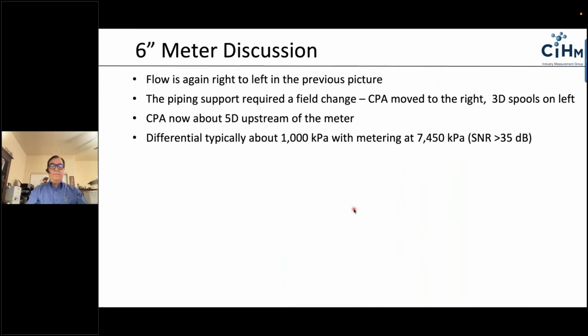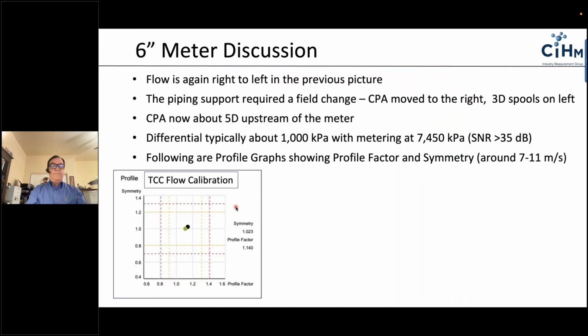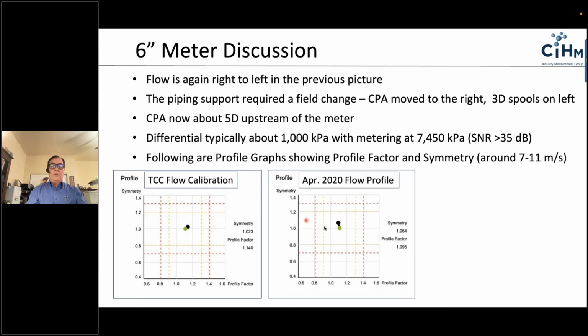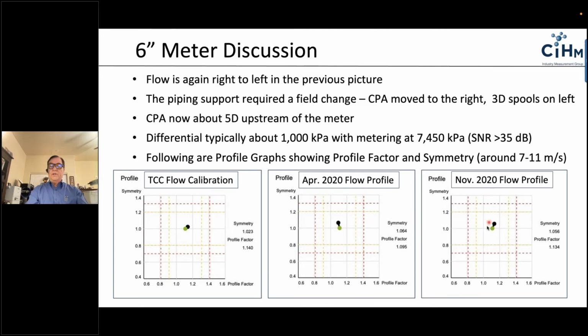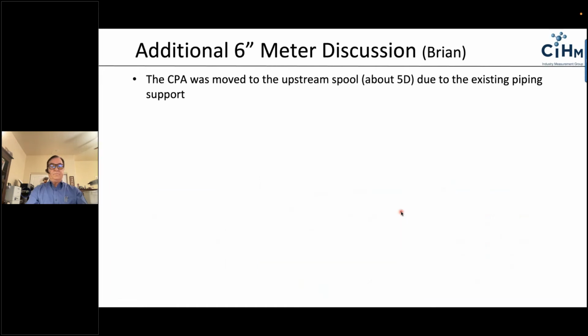Okay. So here's the flow calibration profile at the TCC. You can see the symmetry and the profile factor are very normal. Plus or minus a couple percent on symmetry is not abnormal at all. Installed in the field in April, the profile changed a little bit because of the piping change and the eccentric reducer, primarily due to the eccentric reducer. After a few months in service, we can see the profile looks very similar to what it was at that time. So all well within the normal expectation of what you would expect in a field from upstream piping.